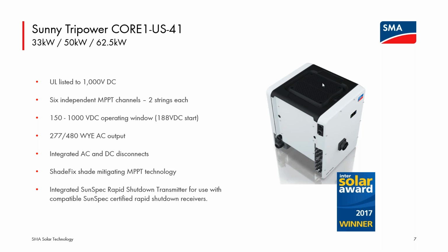And that's really the only preventive maintenance step once this inverter is successfully installed, to make sure that airflow path remains clear throughout the operational life, that debris has not accumulated at the bottom or on the top to block that airflow path. This inverter is a commercial inverter, so it is rated up to 1,000 volts DC. The inputs, you can see the bulkhead inputs here on the right lower of the inverter.